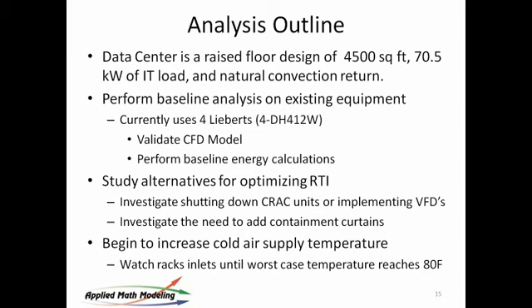We see this a lot, don't we? We do, yeah. Way too much air. Way too much air, way too much cooling. Very common. Because what often happens, most always happens, is the design team that built the data center, that laid it out, built it for worst case conditions, right? Because of course they want to make sure under worst case conditions that it handles the situation. And then the owner takes over and puts in 7 racks and turns all the units on. Yeah, or they're lightly loaded. That's the other thing that people can't really anticipate.